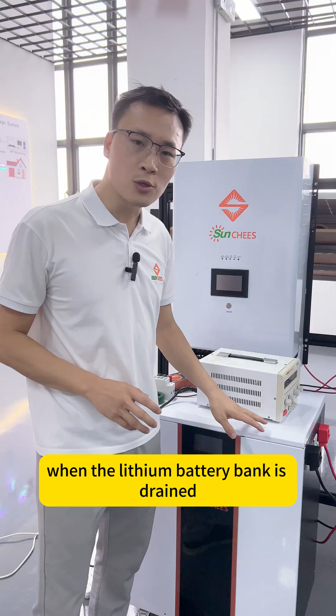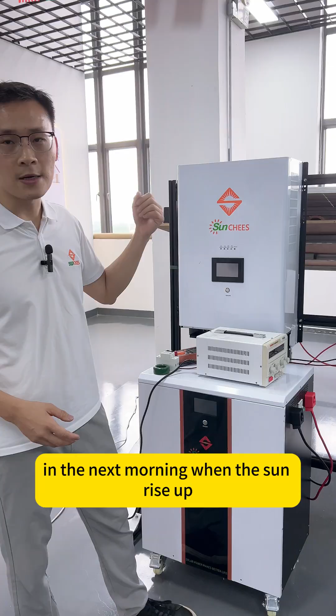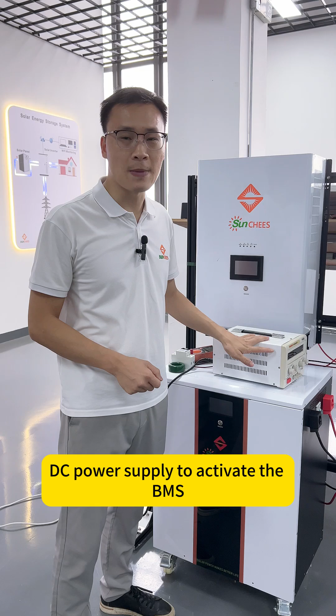This makes the lithium battery bank's real lifetime much longer than an ordinary battery bank. The third special function is that our hybrid inverter has an activation function. When the lithium battery bank is drained and the BMS goes into protect status, the next morning when the sun rises, our hybrid inverter will automatically use solar power to activate the BMS. No need for people to use a DC-DC power supply to activate the BMS and turn on the system again—it's automatic. Next, I will do an experiment to show you how the system works.